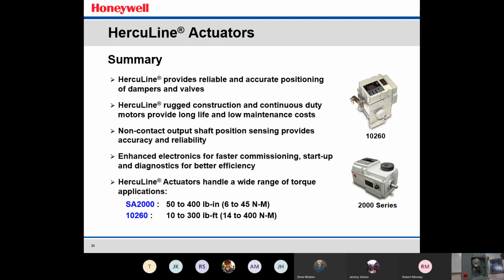So in summary, the Herculine 2000 and 10260 actuators that Honeywell provides, again, provide very reliable and accurate positioning of the final control elements that you have hooked up to your PID loop. Rugged construction design, continuous duty operation. Remember that's a big one, especially if you have high ambient temperatures. These actuators do not have braking mechanisms in them, whereas other lower cost actuators have brakes that can deteriorate as the temperature increases. Non-contact output shaft positioning, enhanced electronics for faster commissioning, startup diagnostics, better efficiency. And again, the Herculine 2000 has models that range from 50 to 400 inch-pounds, and the 10260 ranges from 10 to 300 foot-pounds.